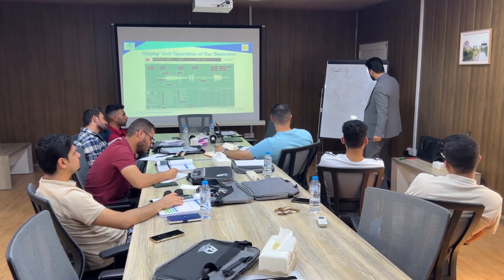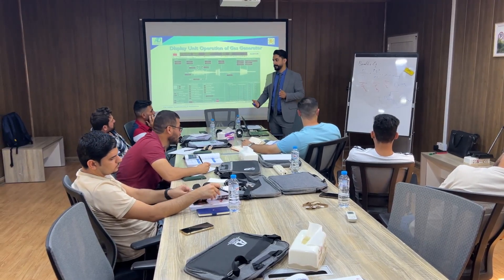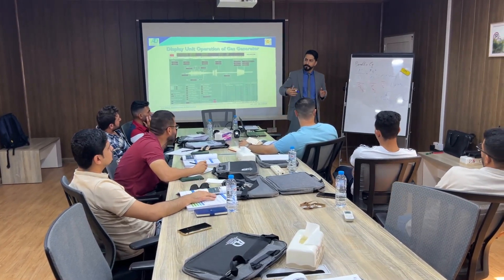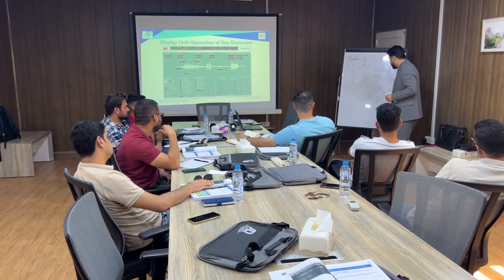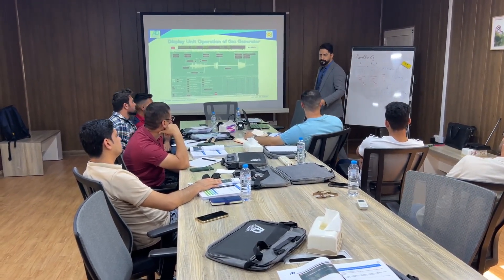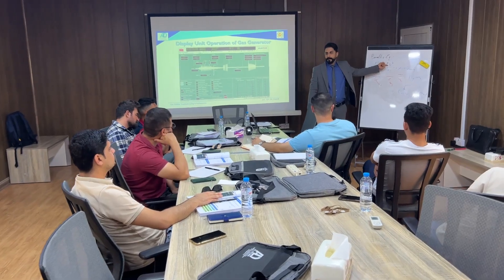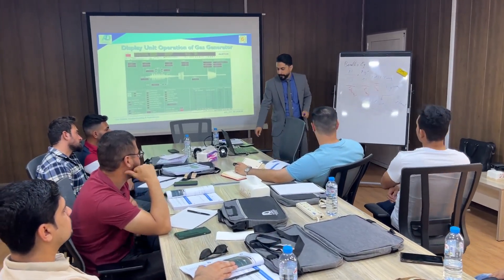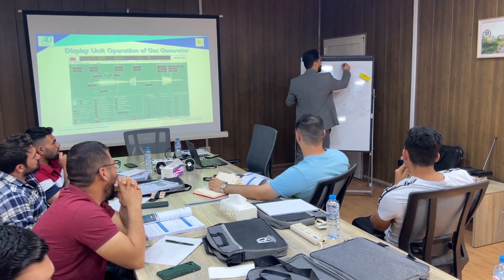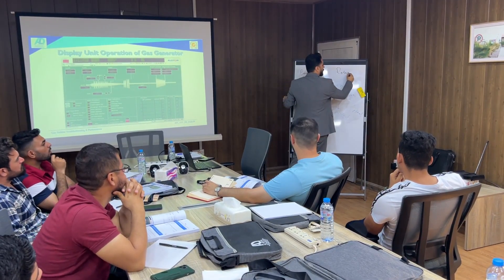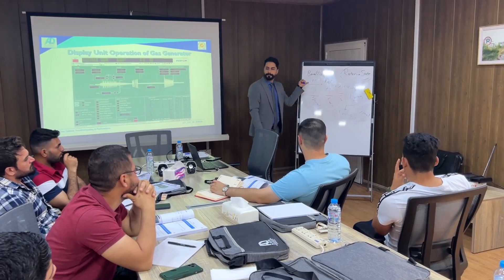These two main types of compressors are used for the compression section of a gas turbine. In 99% of situations, the axial type is preferred because it is more near to the isentropic process — as we discussed yesterday with isentropic, isothermal, and polytropic compression processes. These compressors are able to increase the pressure step by step across different stages. First, the velocity is increased by the part called the rotor, and then by using a stator, we change the velocity to pressure step by step.